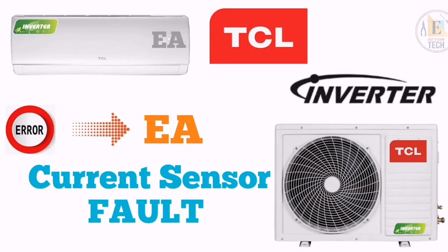When you see error EA in your outdoor unit, at that time you can check your refrigerant first of all, because when your refrigerant is less, that time also it shows the error EA. And even when our inverter unit V1 PCB is not good, that time also it shows the same error. First of all, check the refrigerant. If your refrigerant is not perfect, then recharge the refrigerant and start the unit. And again, if it's showing the same error, then you check the V1 inverter unit.